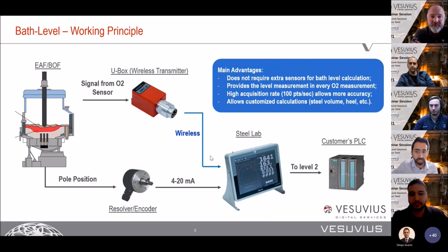We need an automatic immersion, so we need a manipulator. In this manipulator, we must have a position sensor, which can be a resolver, an encoder, or in some cases an inclinometer, which will transmit via 4 to 20 milliamps - an analog transmission, because it's actually the most reliable in terms of timing for our steel lab.